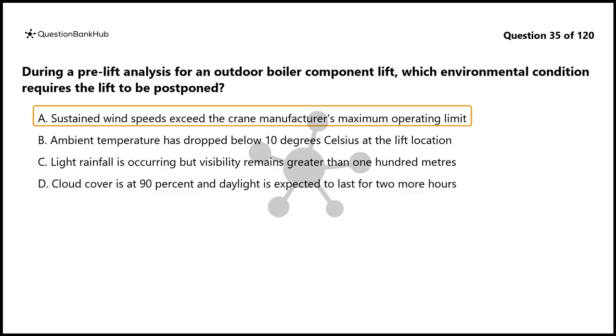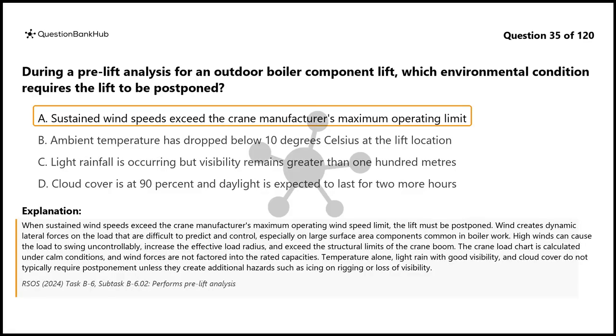The correct answer is A. When sustained wind speeds exceed the crane manufacturer's maximum operating wind speed limit, the lift must be postponed. Wind creates dynamic lateral forces on the load that are difficult to predict and control, especially on large surface area components common in boiler work.